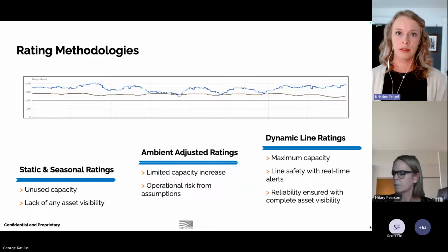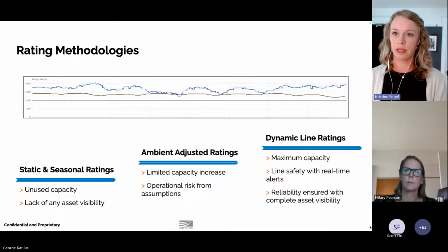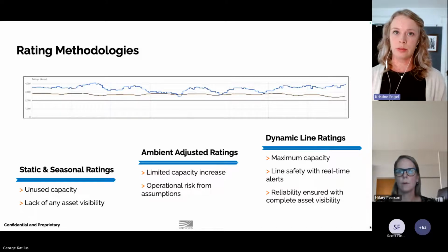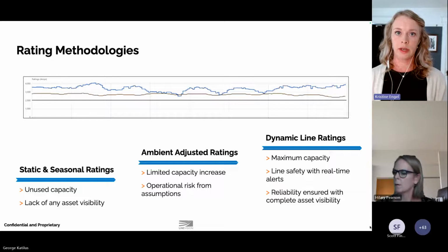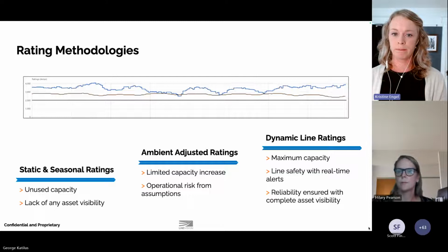CIGRE recommends using 0 meters per second at night and 0.4 to 0.5 meters per second during the day for ambient adjusted ratings, in the absence of a detailed weather study on your system. Those numbers are set low to ensure you're not encountering periods where capacity is overstated and you're at risk of overheating.